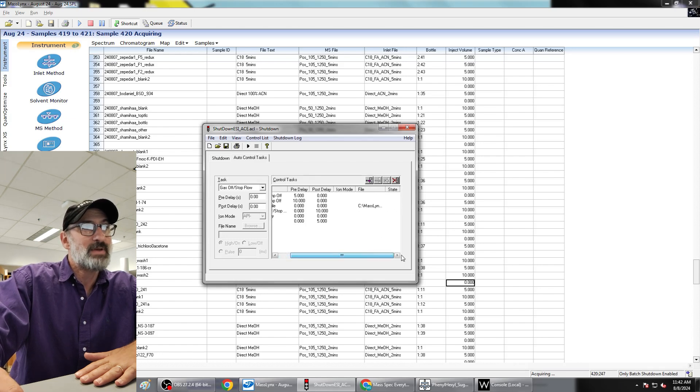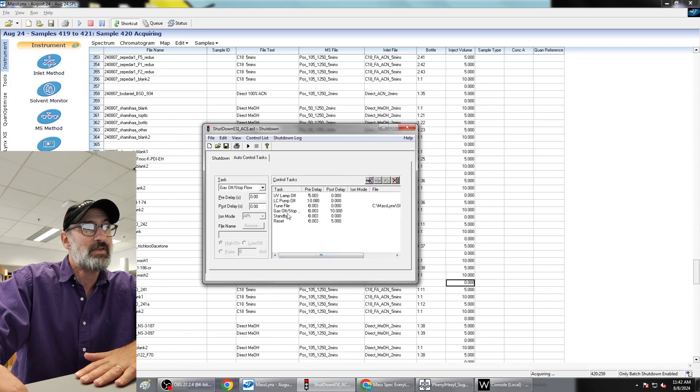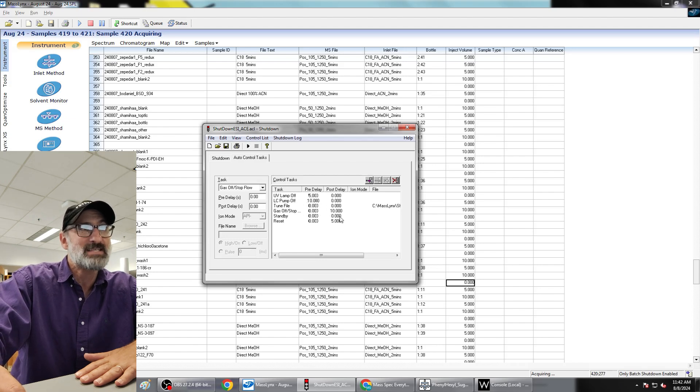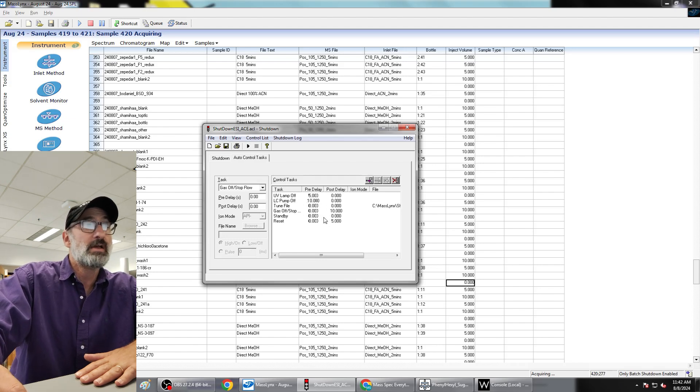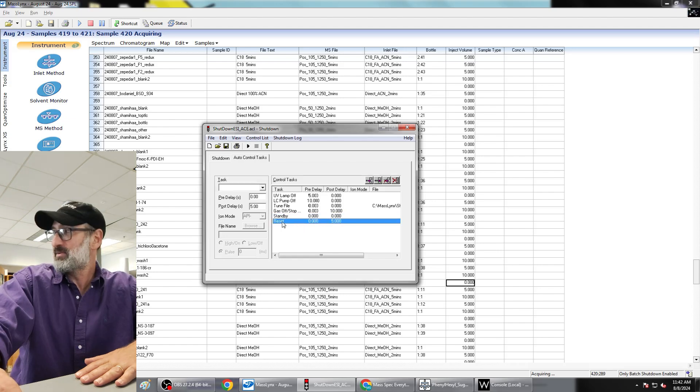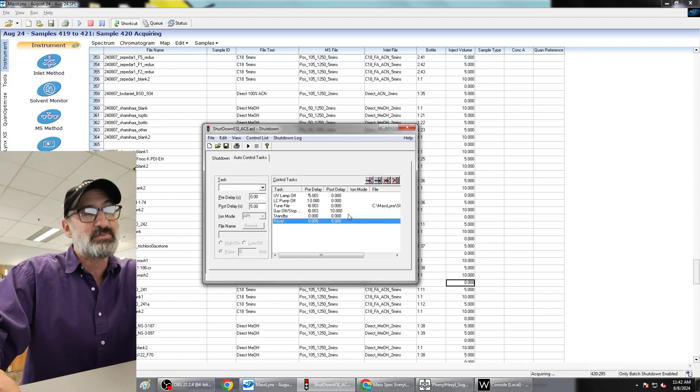Then you're going to tune file. There's this mass spec shutdown tune file that a lot of people like to put in there, so that just turns it to the shutdown tune file there. Gas turned off ten seconds post delay, so you're getting a ten, twenty second delay between the pump being turned off and the gas being turned off. Standby is at zero. And then reset. You have to put the reset in at a five seconds post delay. I don't know why. I don't know why this is, because this is what worked.